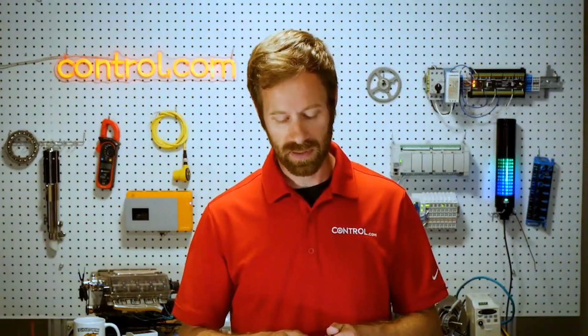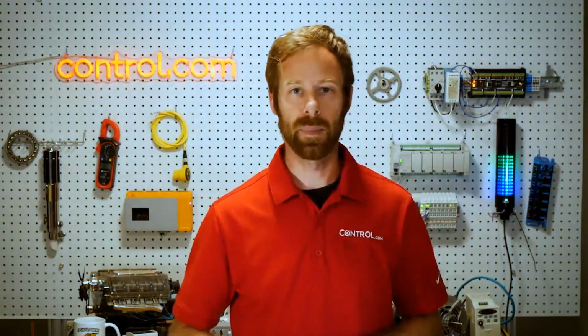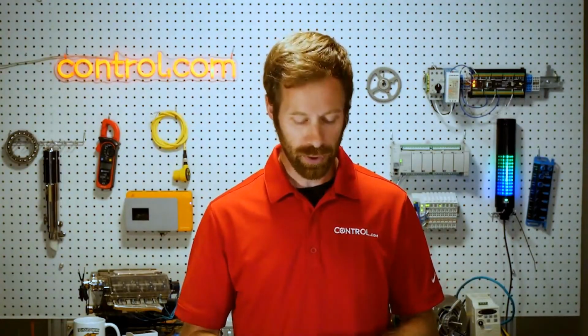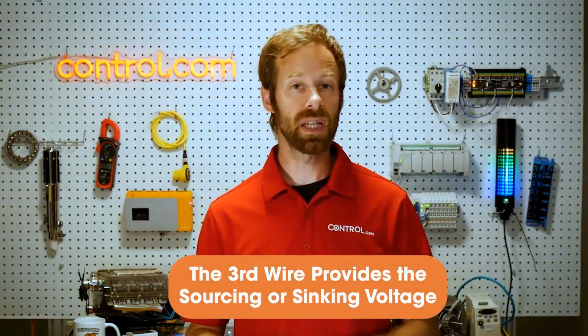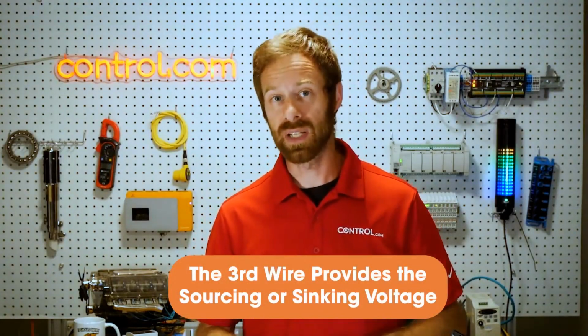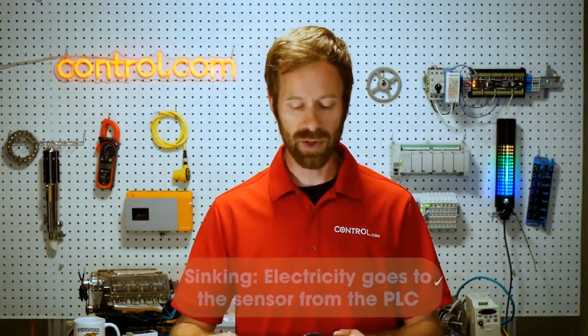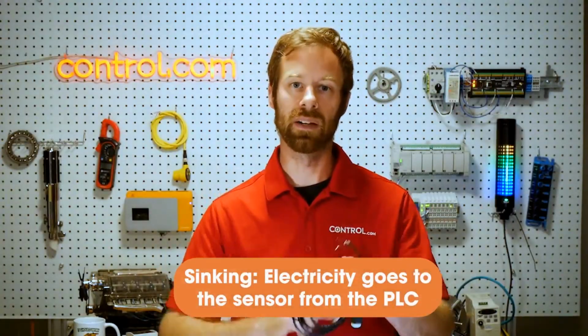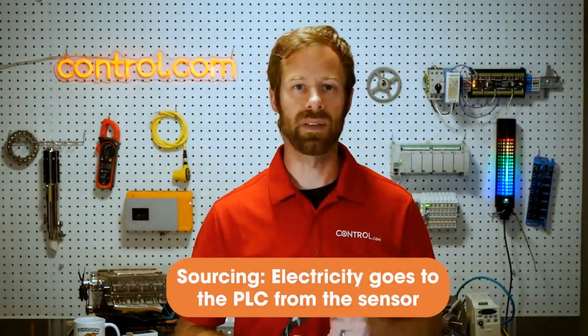So for that reason, we provide a plus and a minus, which come directly from the power supply. So that 3rd wire in our 3-wire sensor provides our sourcing or sinking voltage, like we discussed before. Sinking means the electricity can come to the sensor from the PLC. Sourcing means that it goes to the PLC from the sensor.